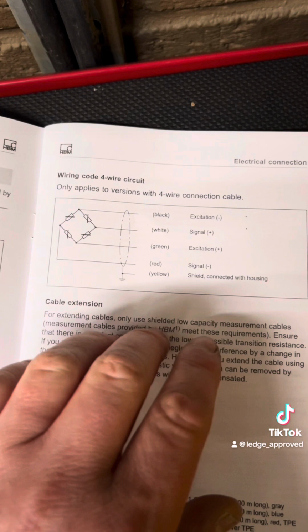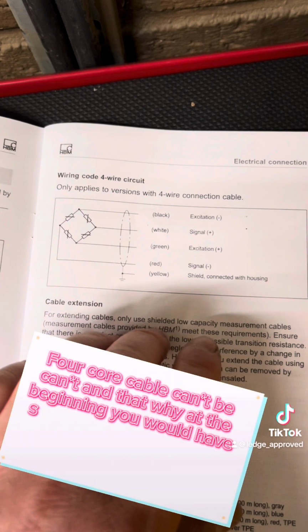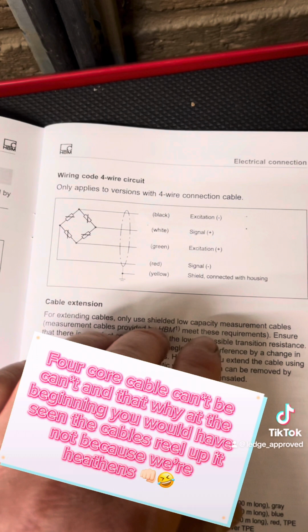So there we've got the 4 core, and this is actually no different. You've got your inputs and your outputs. This one can't be cut because it uses the resistance value of the actual cable itself. Where the 6 core, you can cut it because it monitors that voltage drop.